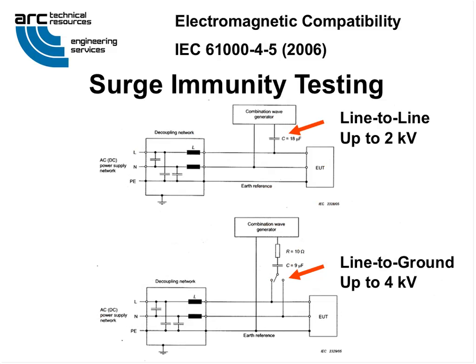AC or DC mains testing is shown here. The upper diagram shows a combination wave generator connected to a power line coupling for line-to-line coupling. Associated decoupling is shown at the left. The lower diagram shows the generator connected line to ground, sometimes called common mode, on power lines.